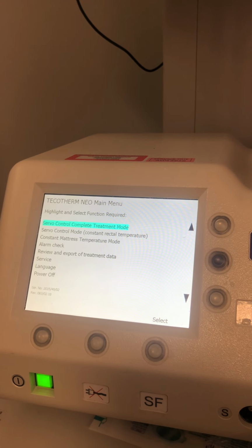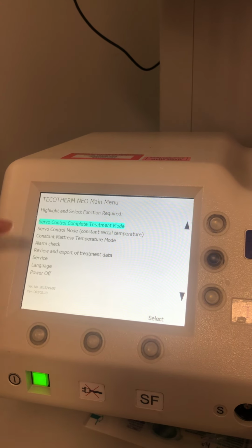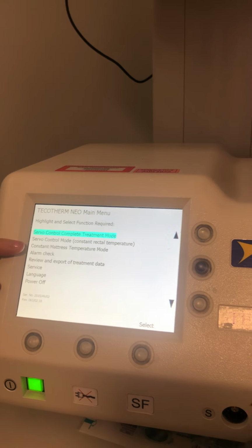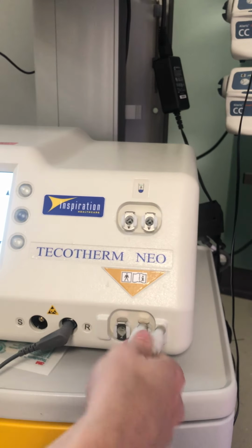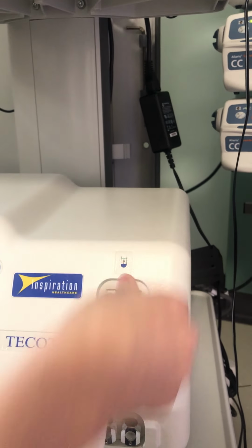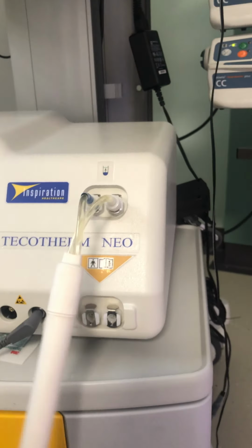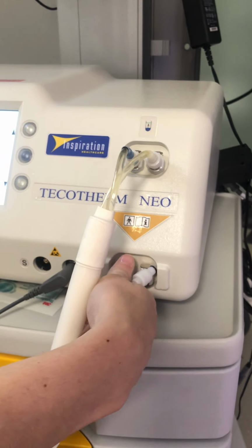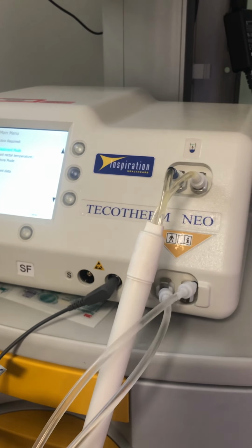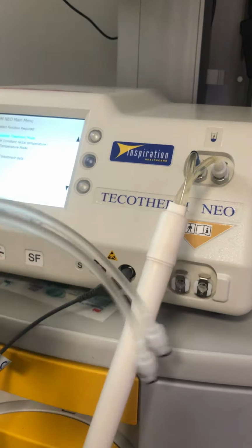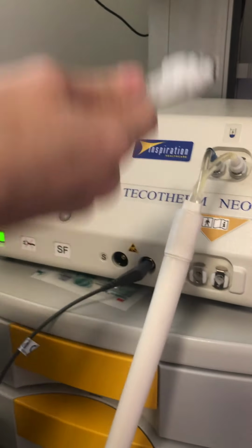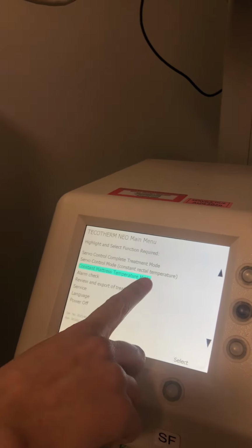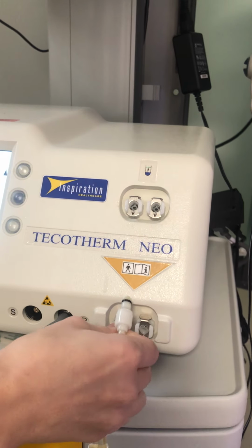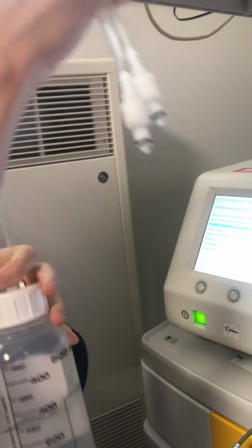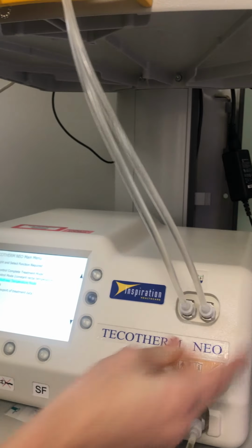Then you'll need to clean it. Exactly the same way that we filled it, go into the constant mattress temperature mode. But this time you put the mattress onto the top ports and an empty bottle onto the bottom ports. The mattress will empty into that bottle. All you need to do is keep an eye on that bottle, and keep unplugging it to empty the bottle and refilling. Again, with it still in constant mattress temperature mode, once you're happy the mattress is empty, you swap it back, clip them back into the bottom, and put new water in your bottle and attach that back onto the top, and it'll fill the mattress back up.